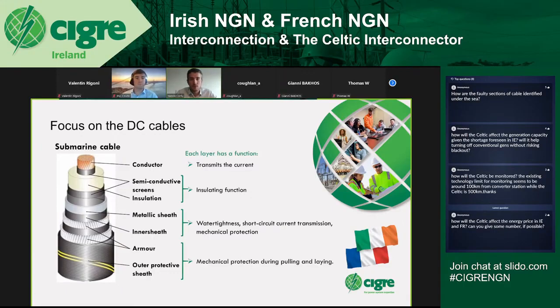The conductor is here to transmit the current. It's made of copper or aluminum. Then we have the insulating part, which is composed of 3 layers: semi-conductive, insulation. Here it's XLPE. We then have the metallic sheaths and the inner sheaths, which help with the water tightness of the cable, transmit the short circuit current in case of failure, and also provide mechanical protection of the inner part of the cable, so the insulating layer, which is the most critical part. And then, because it's a submarine cable, we have armor and another outer protective sheath. This armor is here for the mechanical protection of the cable during pulling and laying. We can move on if you want.